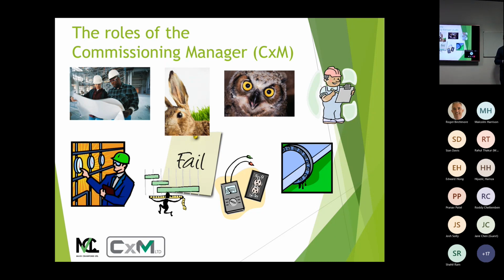We review the installations. Once we've done the design review and pointed out there needs to be some more valves, test points or dampers in the wrong place, we then check the shop drawings have incorporated those requirements. As the installation takes place, we wander around site to check things are actually being installed in the right way and valves are in the right way around.